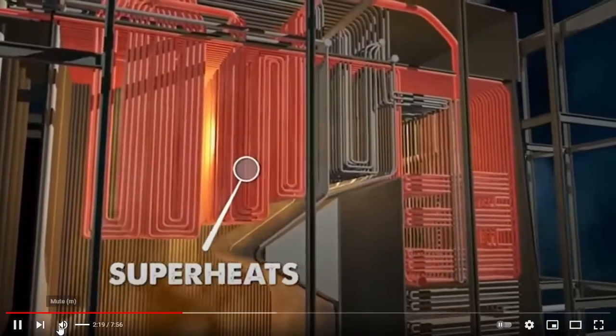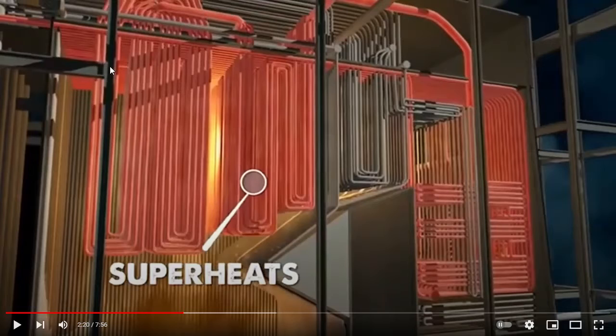Okay, so that steam water mixture, we're concerned about that because we don't want that steam to condense back into water in the pipes and then go through the turbine, because the turbine is spinning so fast that if water goes in there, it'll destroy the turbine. It'll shred that turbine. So what we do is this thing that's called superheating it.